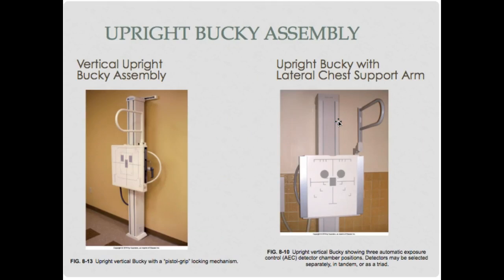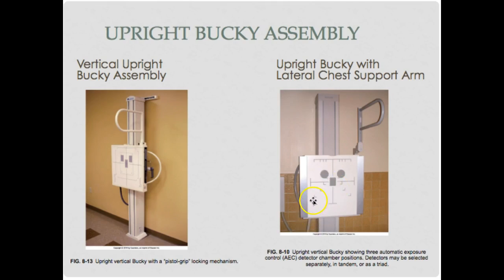The vertical upright Bucky assembly comes in two types with different locking mechanisms. You can see the photo timer cells — two outer cells for the chest and the center one for a lateral chest. Use these photo cells and make sure you're centered properly. The tick marks and lines indicate different cassette sizes.